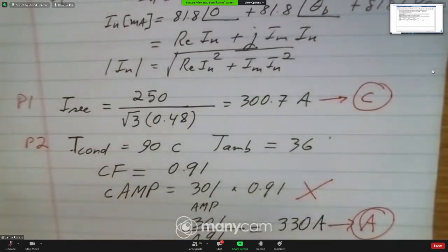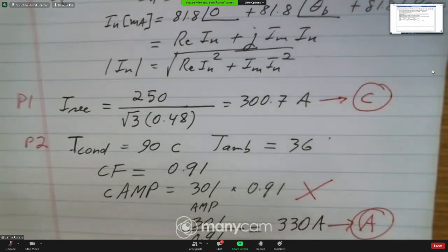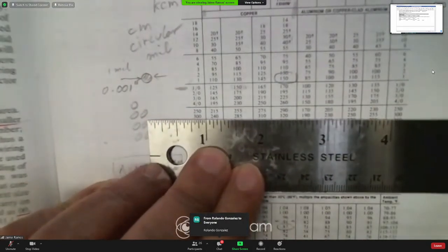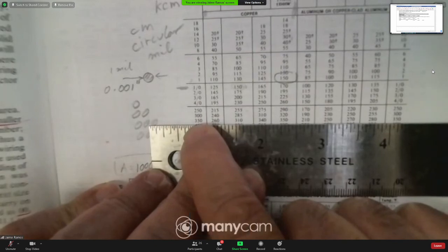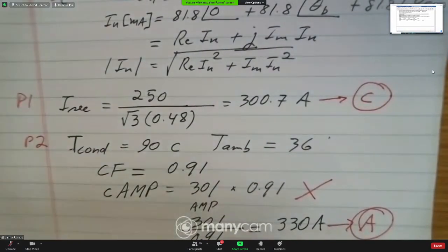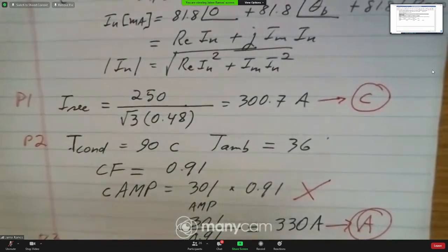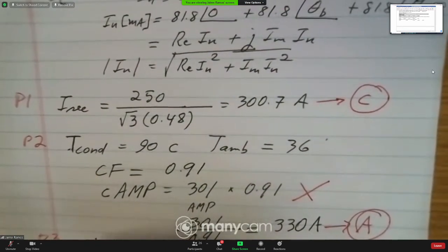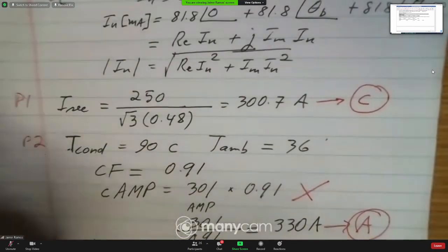So finally, I know I'm over now, just one more minute. So now go to 330 on 90 degrees. So that's this conductor here, 350. So then the rating, the gauge of the conductor is going to be 350 kcm. 350 kcm. Problem 3. Gauge. Cable, 350 kcm. So that's number E.